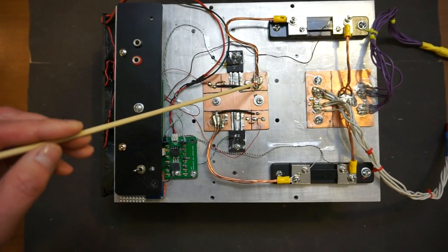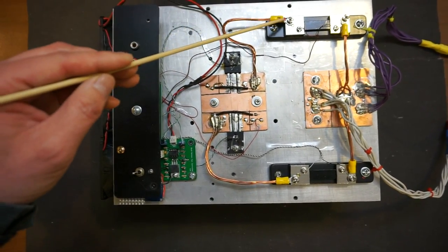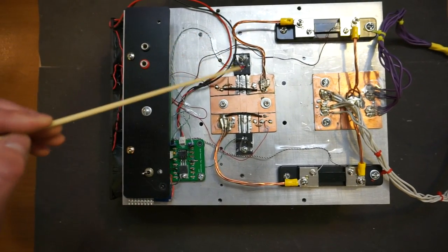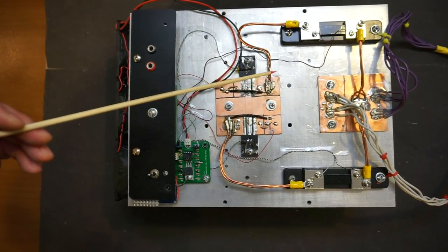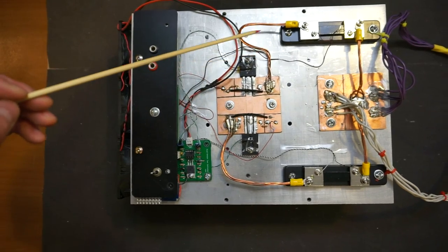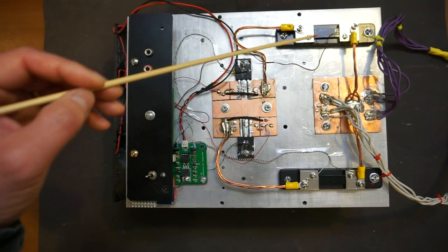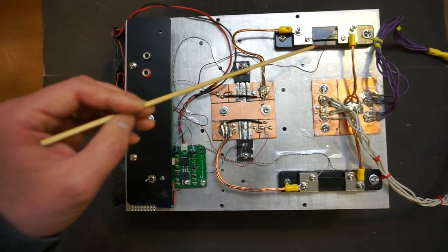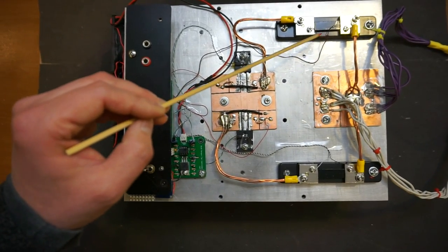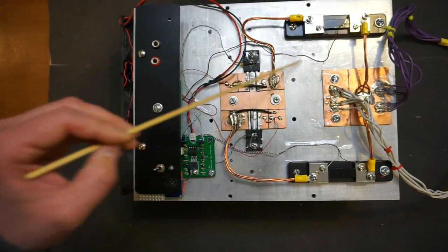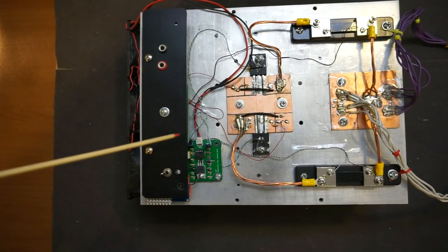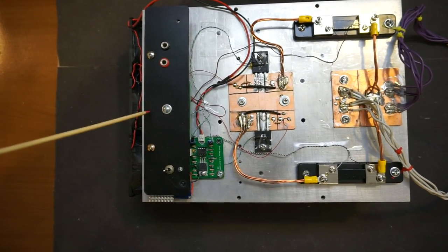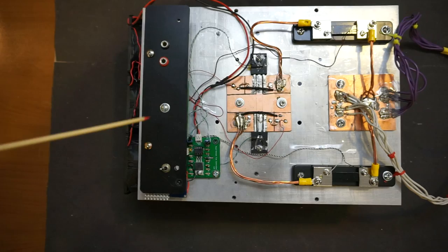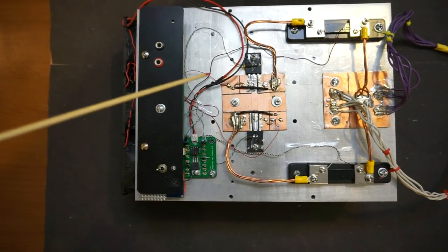We use these very thick copper wires. Each of these is capable of carrying at least 100 amps, and they go through this current shunt. You can see these very thin wires coming from the sense terminals. These go to the op amps, which are underneath here. Of course, I will show you that after this.